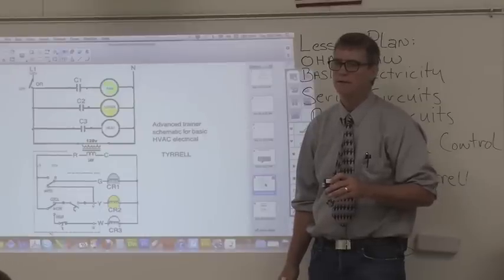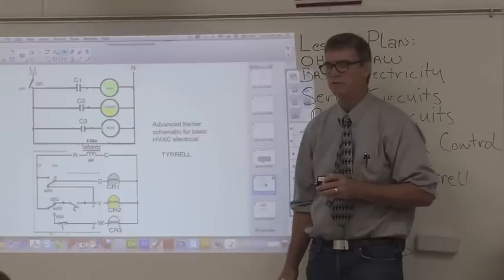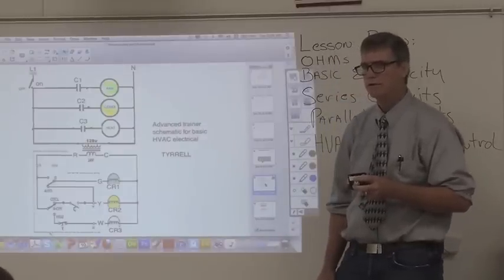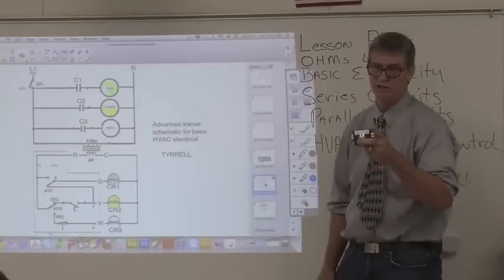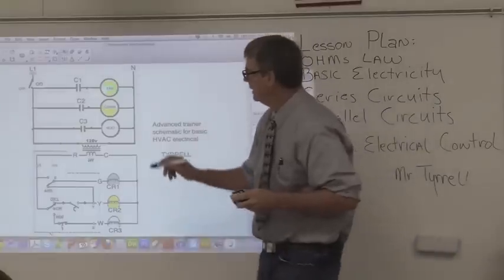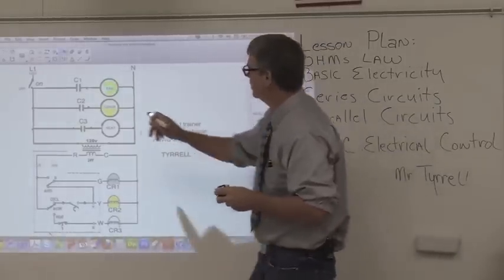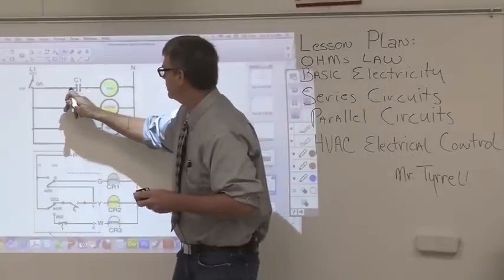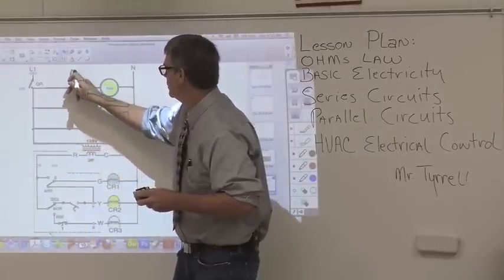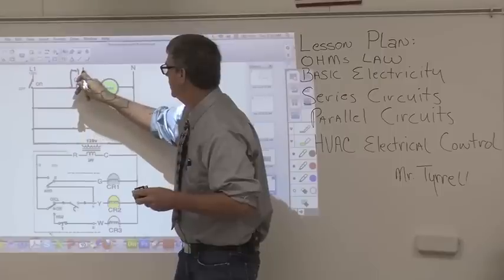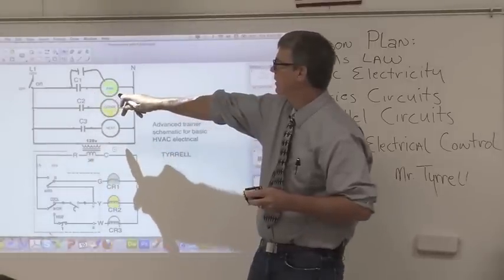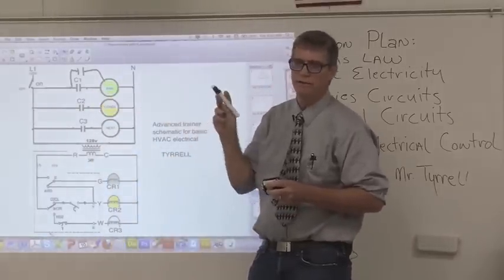Whenever you have it on heat, the indoor fan motor needs to run too, right? That's a good point. In the real world, we are going to have an auxiliary contact, and that auxiliary contact is going to be run in parallel with C1. We're going to call that the fan switch.